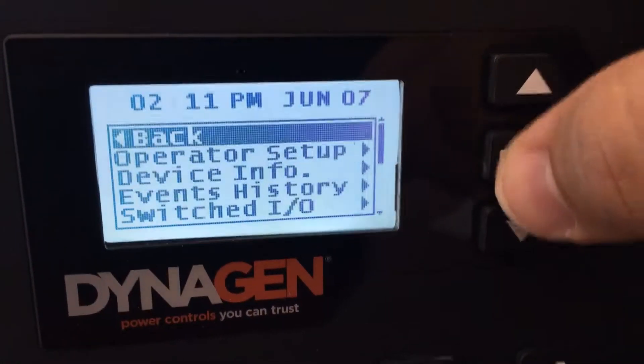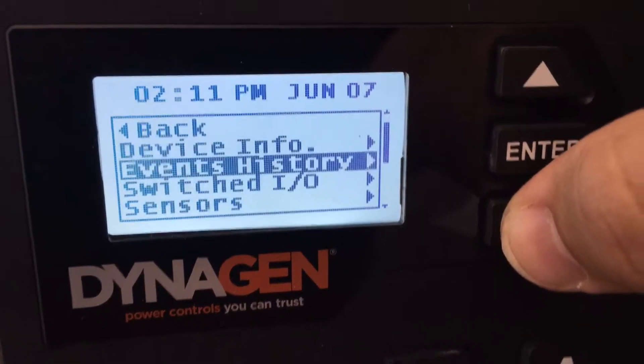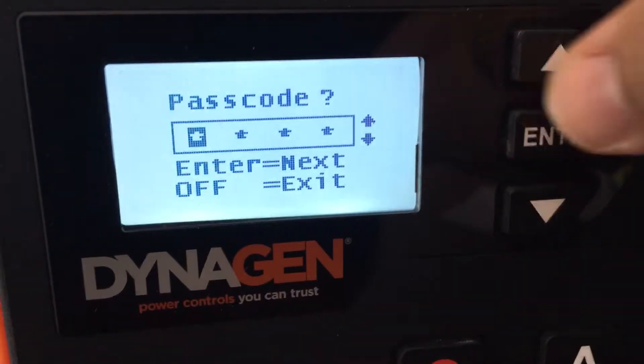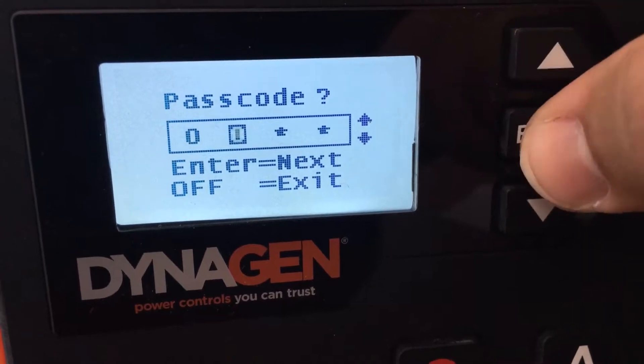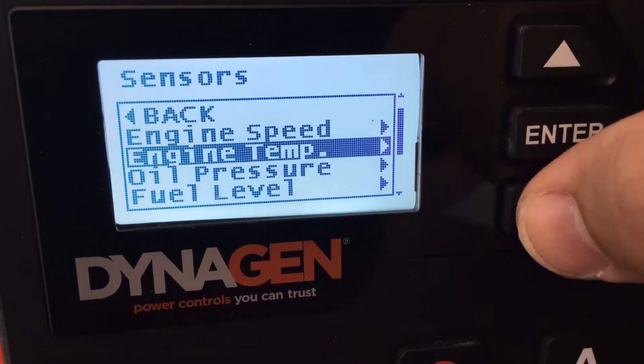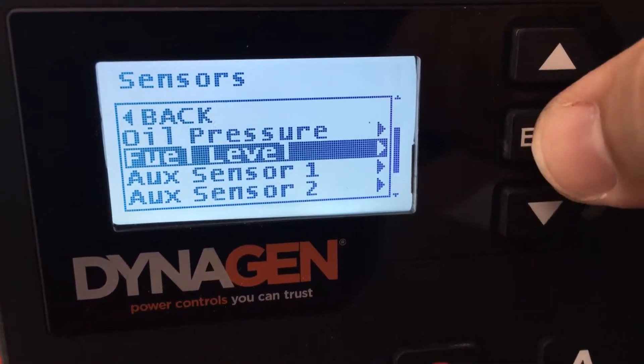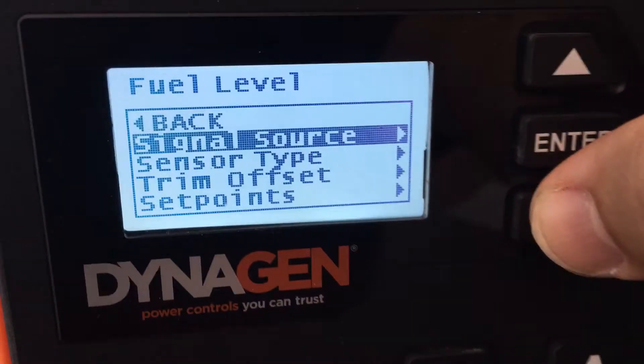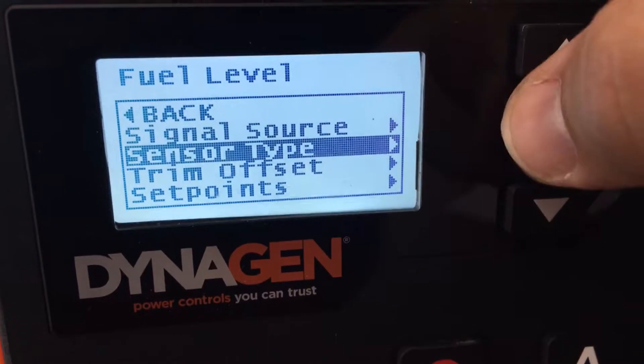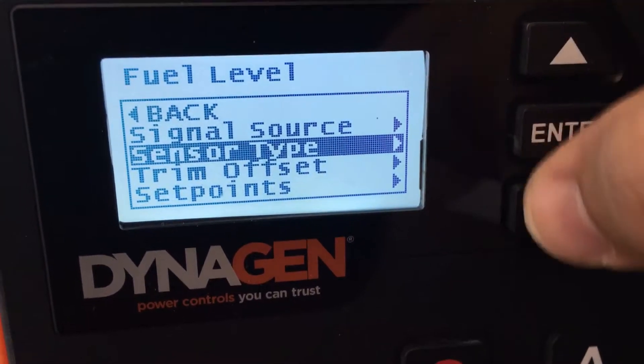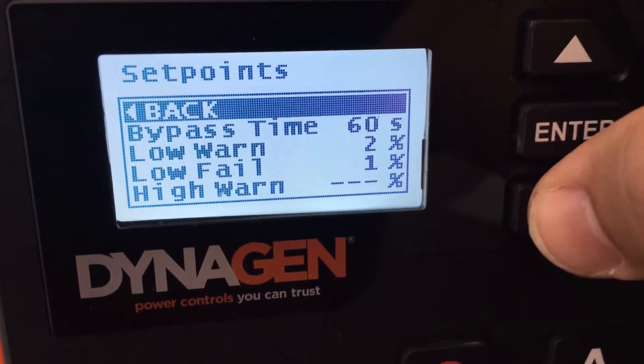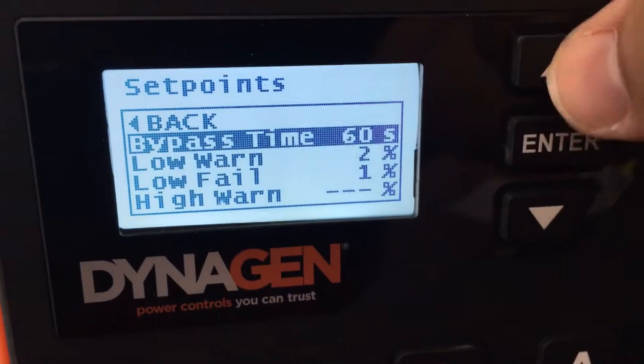Now you can set what those levels are. When you go to sensors, it may ask you for a password — it's four number zeros. So in sensors, we're looking for the fuel level. There's fuel level. The signal source we don't have to adjust; that tells it what input to use on the controller. The sensor type is already set for you. The set points: how long to ignore the sensor, what the low warning level is.